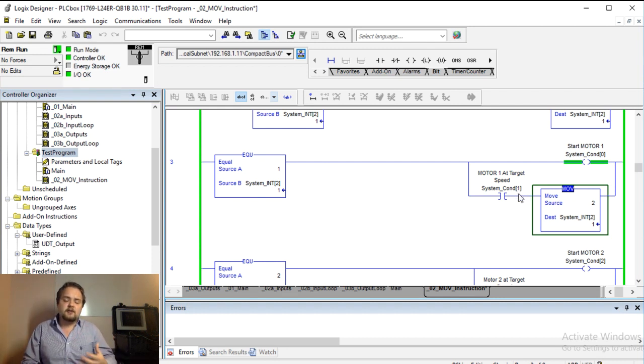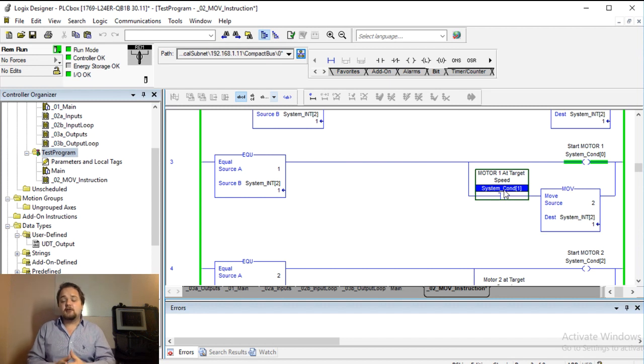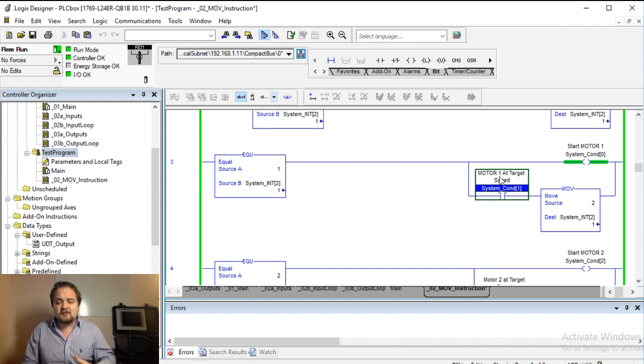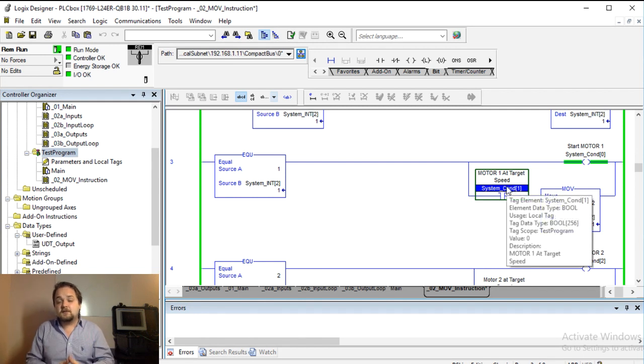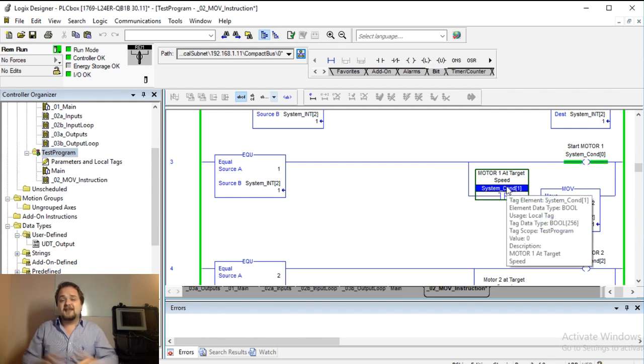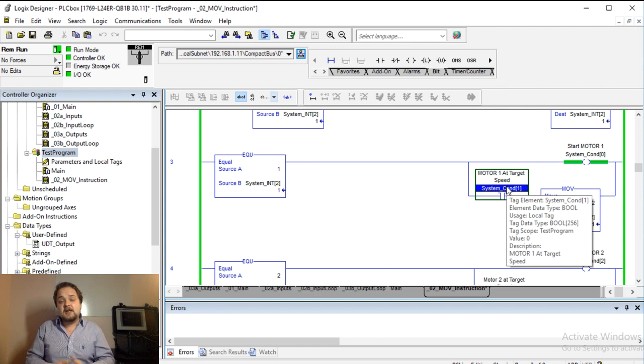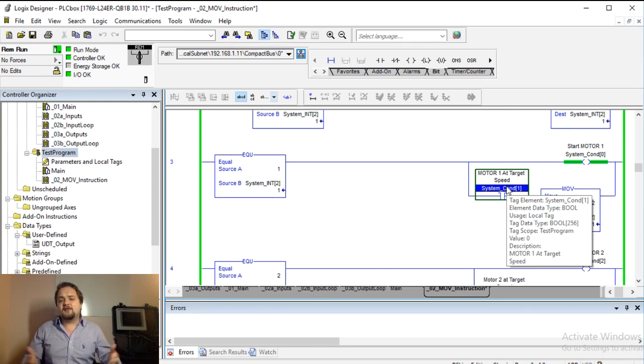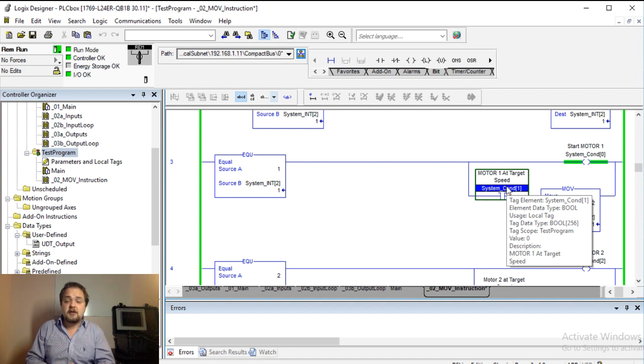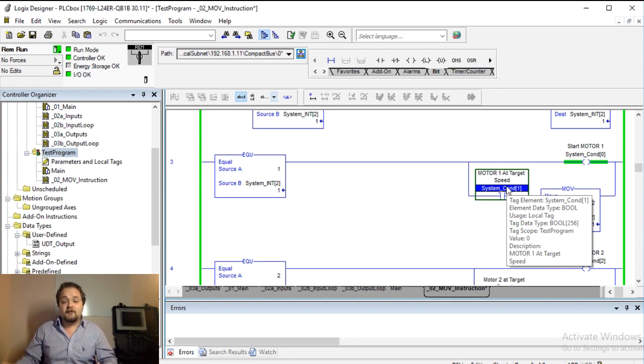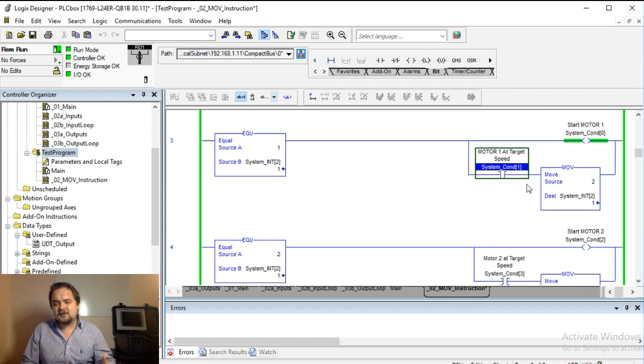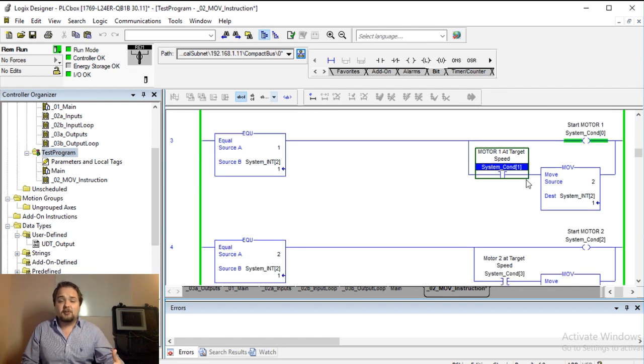So this is a very critical piece of information because here you can implement a very basic timer. For example, if this motor has not been at target speed for, if it takes your motor five seconds to ramp up, if it hasn't been at target speed after 10 seconds you have a certain failure in your system. So you want to shut it down and you want to prevent it from going further.